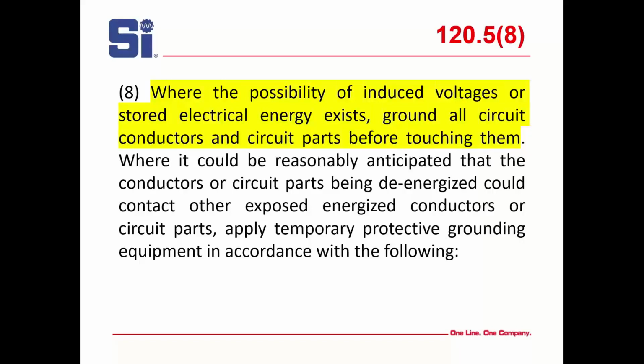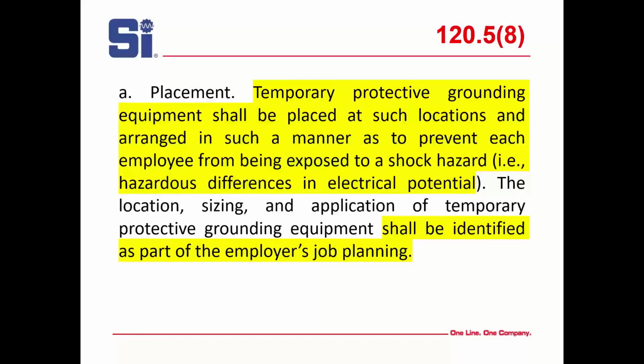Where it could be reasonably anticipated that the conductors or circuit parts being de-energized could contact other exposed energized conductors or circuit parts, apply temporary protective grounding equipment in accordance with the following. So temporary protective grounding equipment shall be placed at such locations and arranged in such a manner as to prevent each employee from being exposed to a shock hazard. So again, primarily we're looking at attaching the ground connection first, and then attaching grounding cable to each of the energized or de-energized lines.